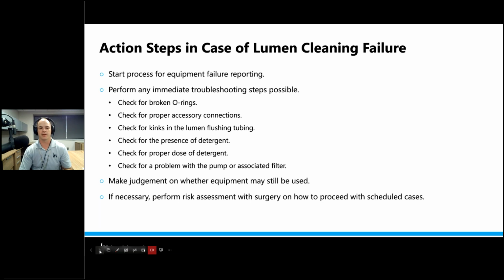So it's really important. When it comes to dirty instruments in the OR, there are many kinks in the chain that can go wrong, and you have to look at point of use care. Okay, so nurses and techs, surgical techs, don't be mad at me, but point of use is foundational. But our automated cleaning equipment, if we know that it's way more effective than our manual procedures, we really need to make sure that our automated equipment is functional. So how are we going to do that? Right, we're going to start a process for equipment failure reporting.